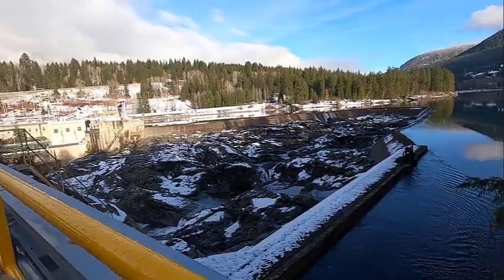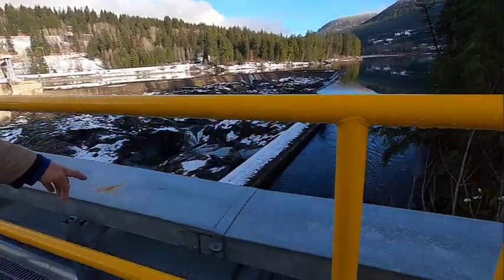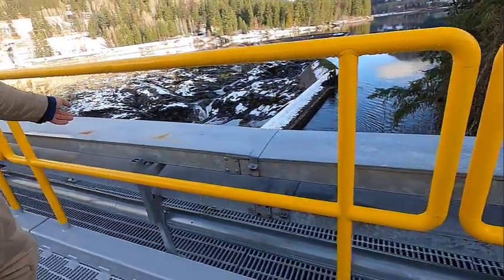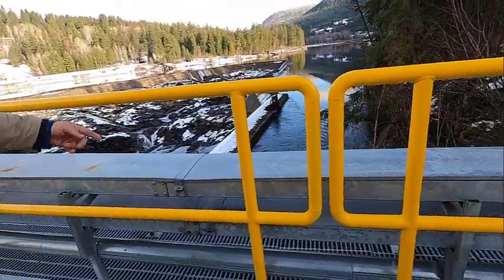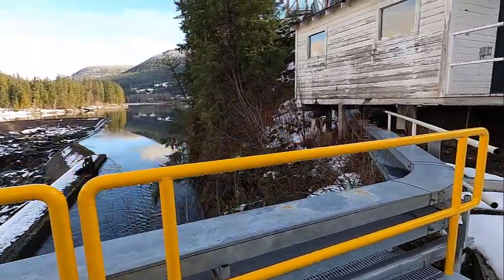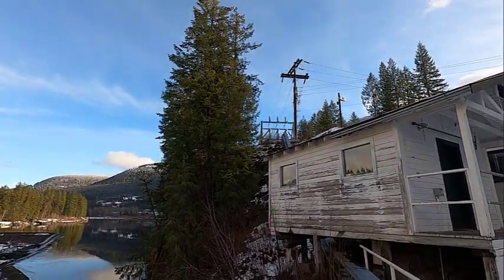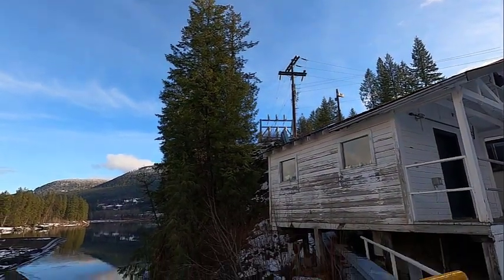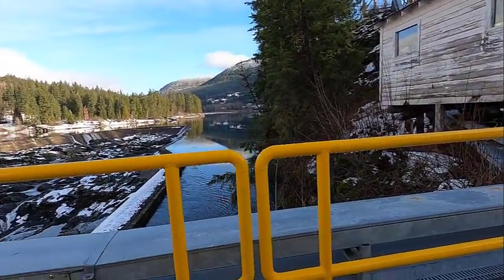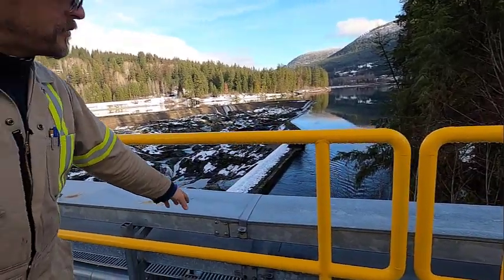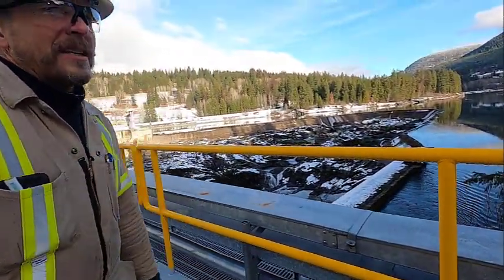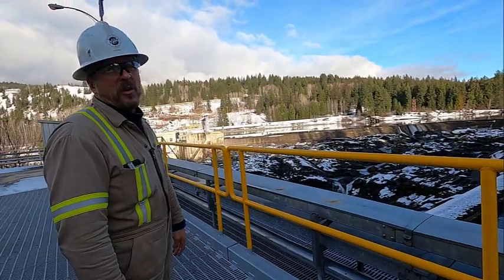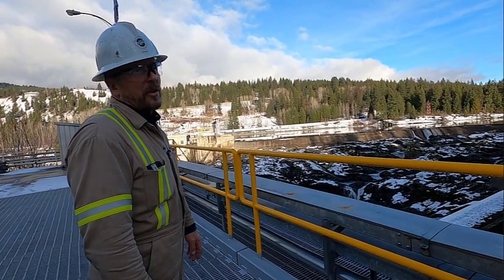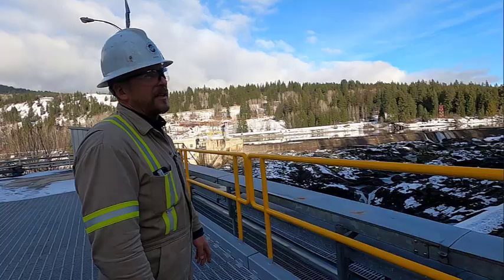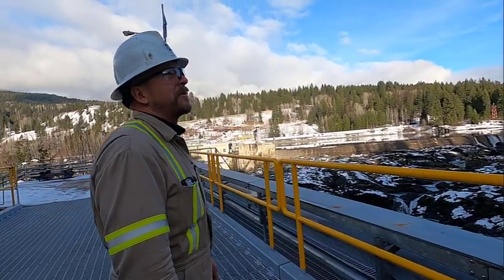So right in front of us here are cable trays. This takes the electricity, the power from the generators up to a substation that's just up over the hill here. So these cables here at 12,000 volts, they're insulated cables, so they're safe within that tray, but that is just a better way of doing it rather than having overhead lines, which are more troublesome near waterways, especially with birds and whatever.